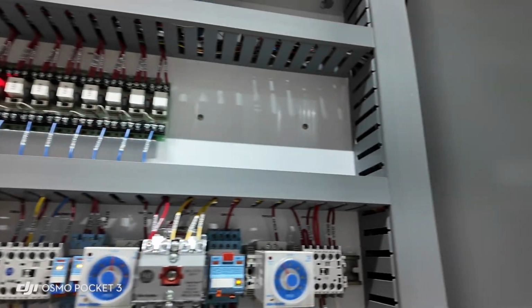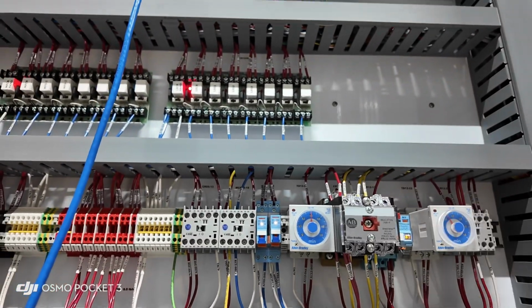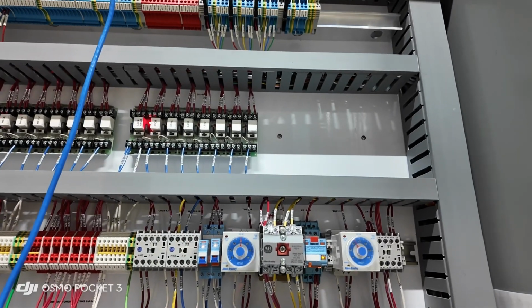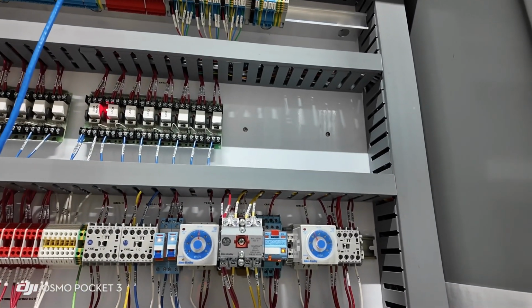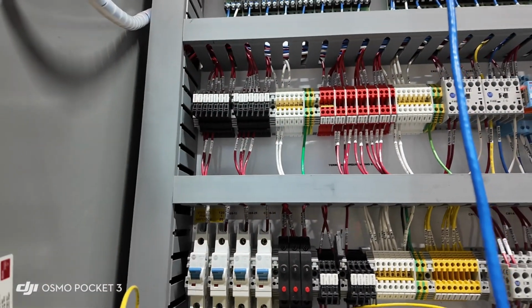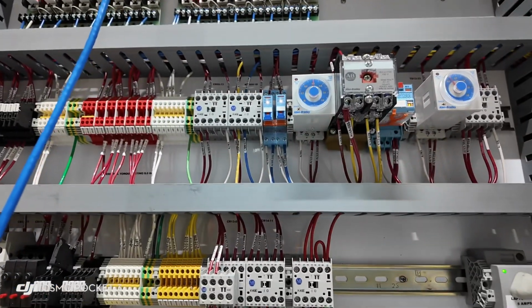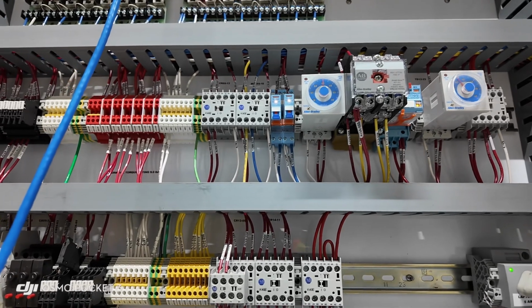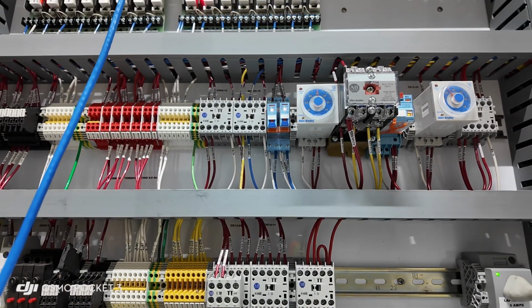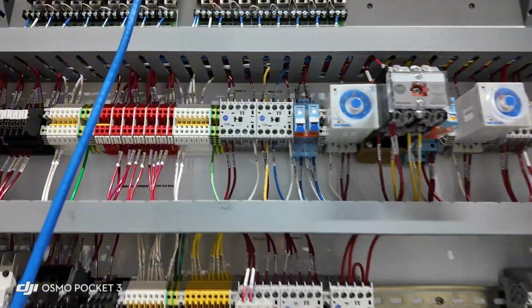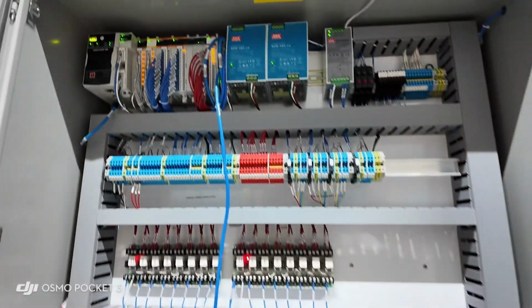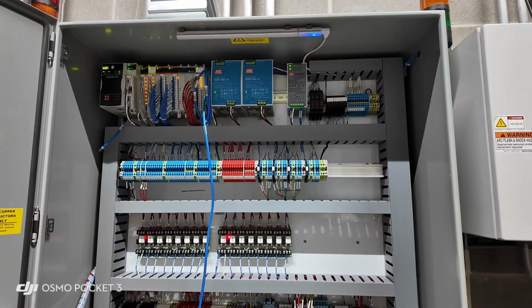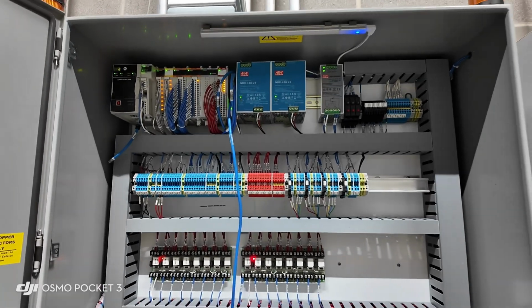And then we have fuses, control relays to control various operations, time delay relays based for our low level and high level shutdowns. No, a bounce of a float won't take the vessel out. Again, control relays and main power distribution breakers. Okay, one of these control relays in here is actually our high level shutdown or safety circuit control relay to shut the compressors down. Okay, so shutting power off to this panel will drop that relay out and cause compressors to shut down in the engine room.